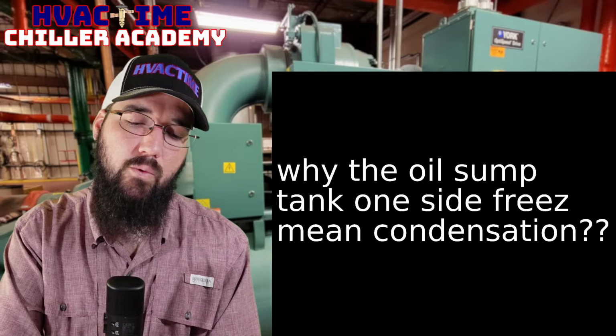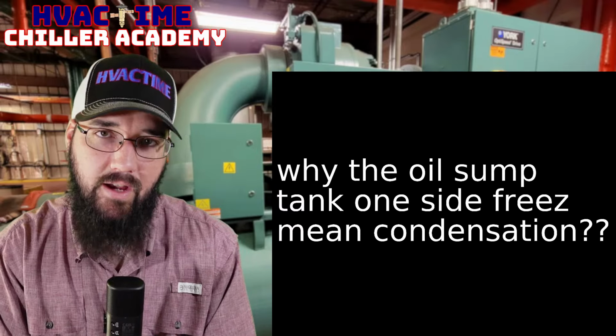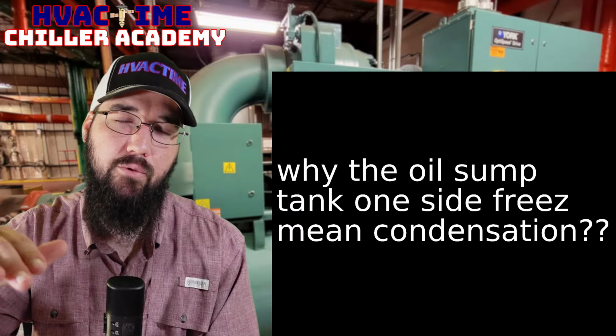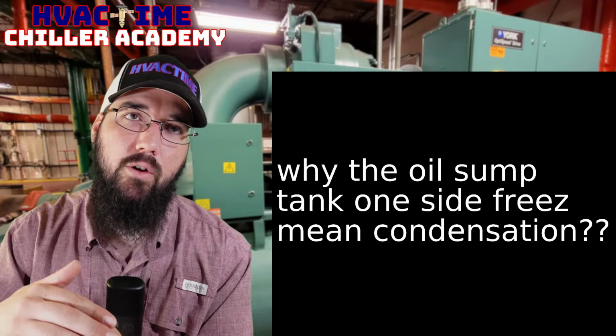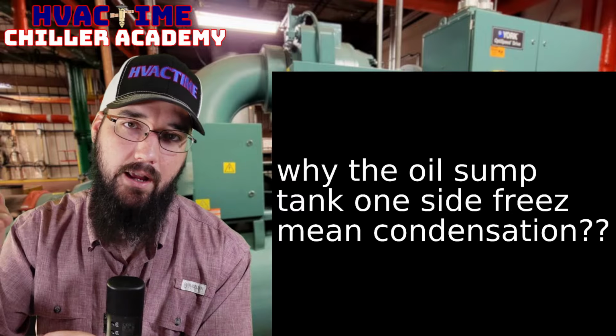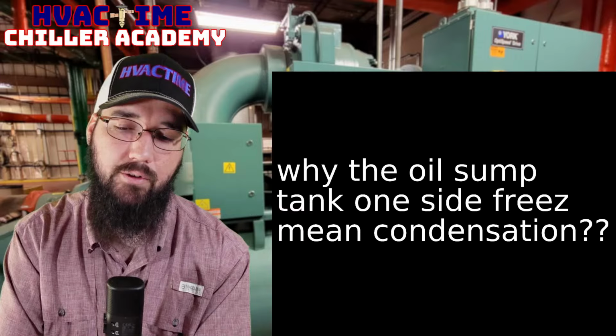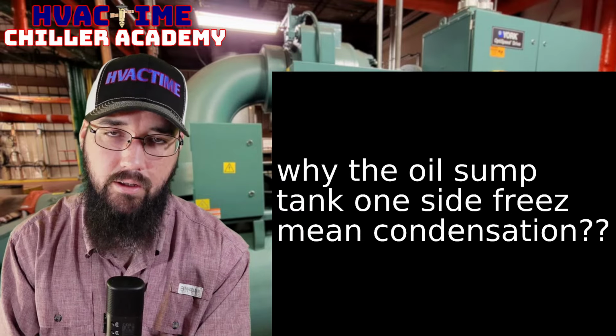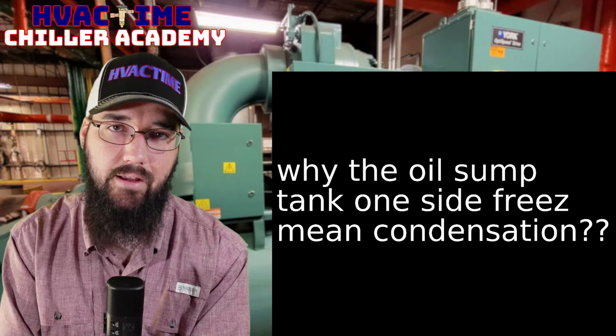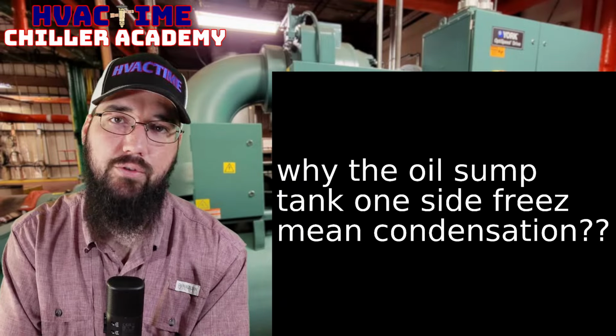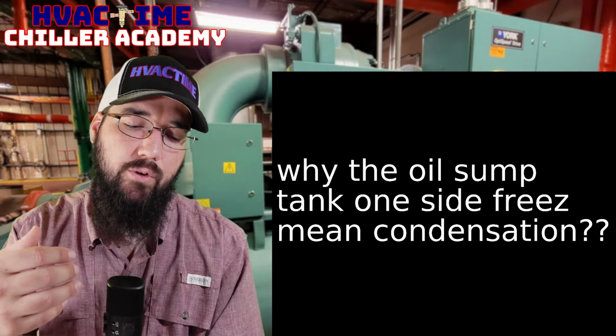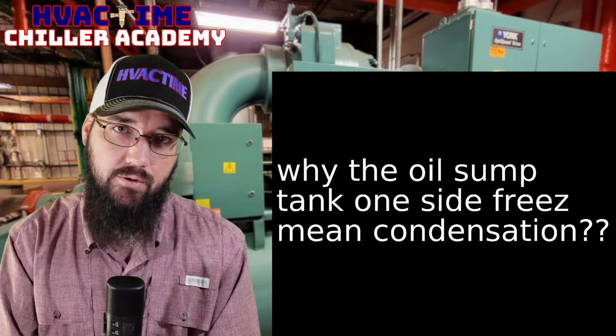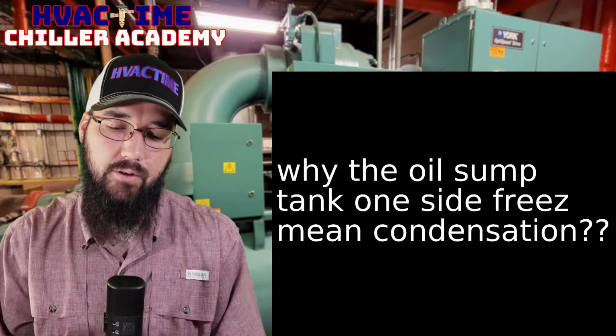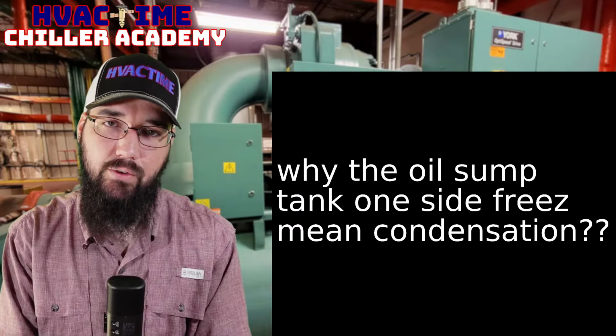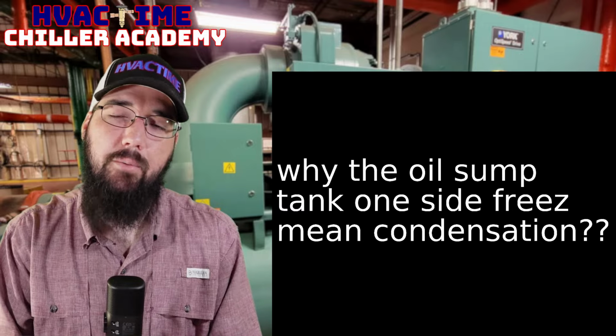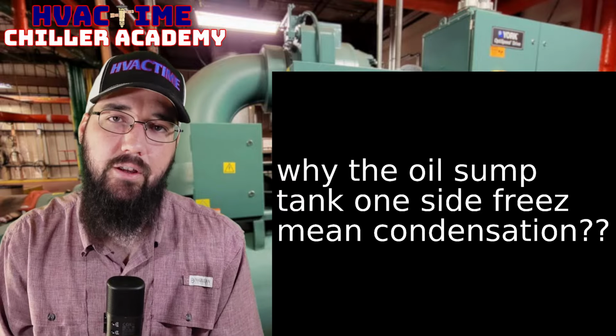So if we get too high of a liquid level in the evaporator, the oil-laden refrigerant gets too high, and we get to the point where the eductor return line is literally only pulling liquid refrigerant back in. And as it pulls that liquid refrigerant back in, we start overloading the eductor circuit, because part of what happens with the eductor is the discharge gas we have coming from the condenser.